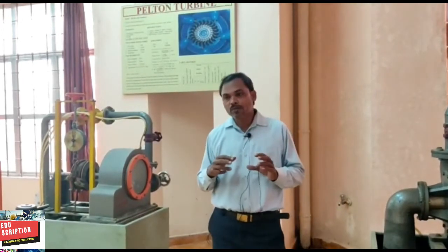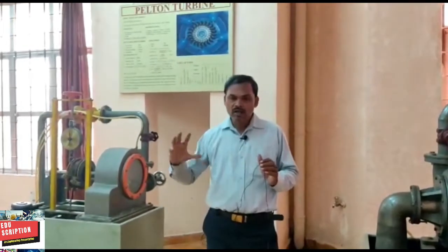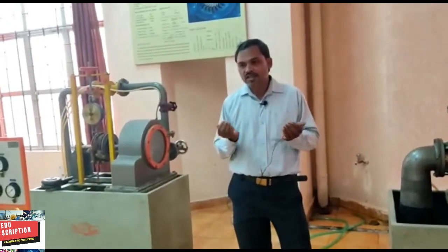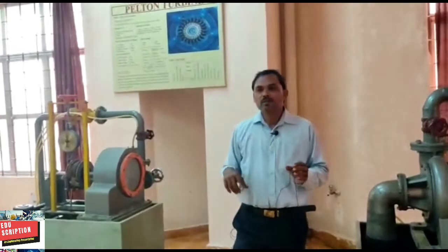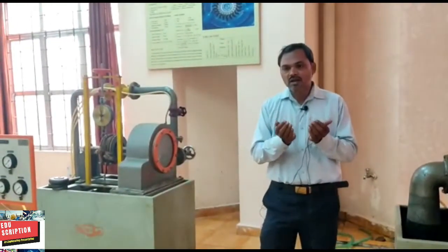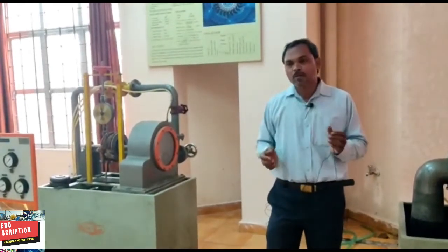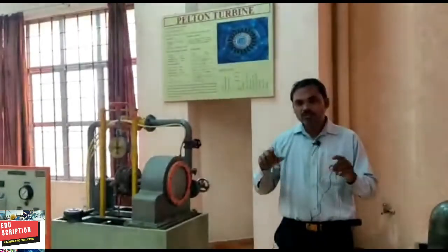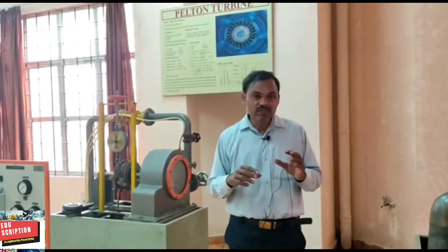The runner consists of a circular disc with a number of buckets evenly spaced around its periphery. The buckets are in the shape of double elliptical cups. Each bucket is divided into two symmetrical parts by a splitter. The jet of water impinging on the splitter gets divided into two equal parts and leaves the bucket with an angle of 165 degrees.